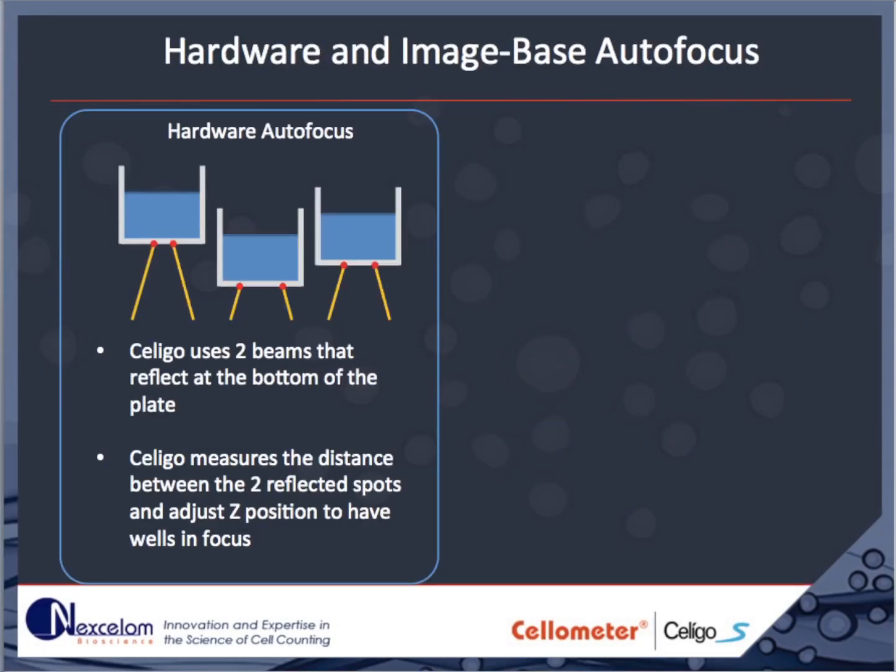The Celigo has two methods for finding the focus in each well. Hardware-based autofocus is used on high-quality plates and works by reflecting two beams of light off the bottom of the well. The distance between the two beams serves as a measure of sample distance from the objective. With this, the Celigo can adjust the Z position for each well so the sample is in focus each time.